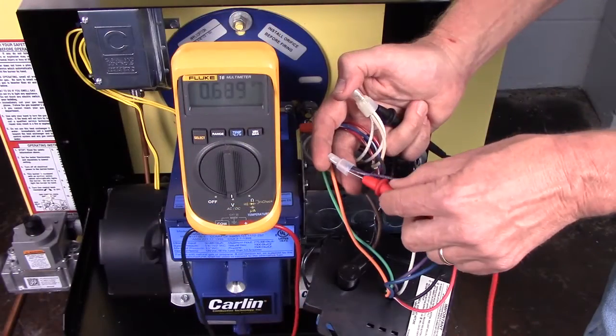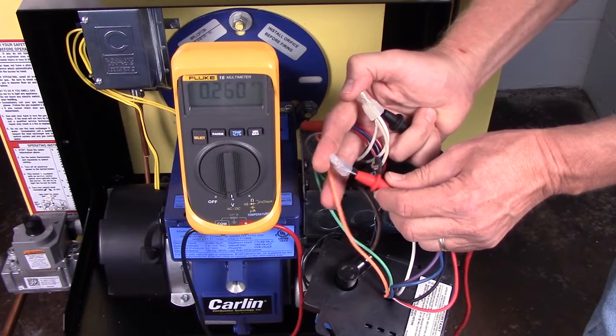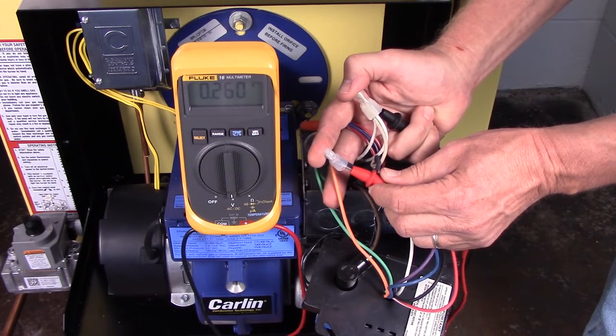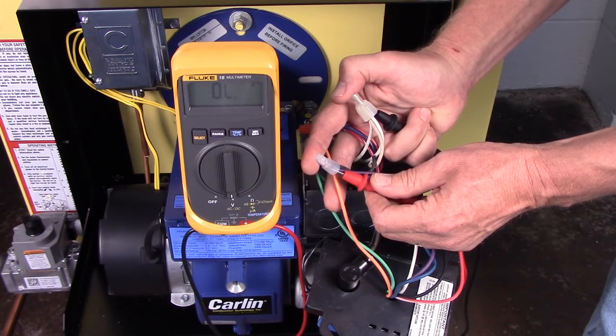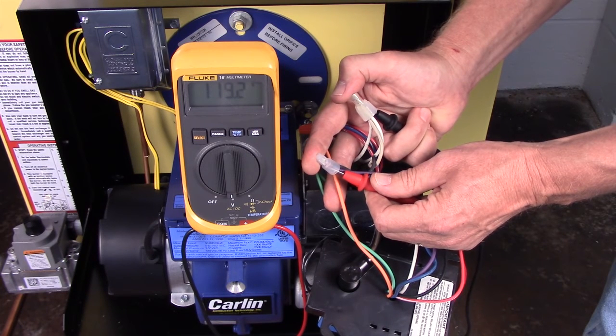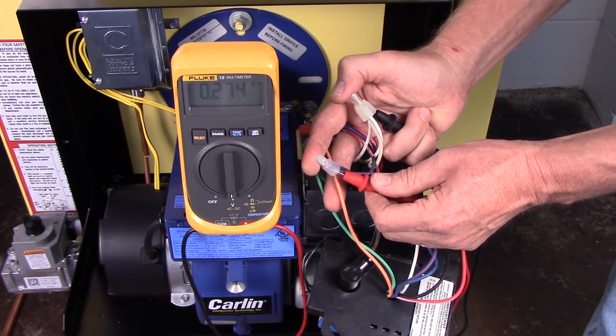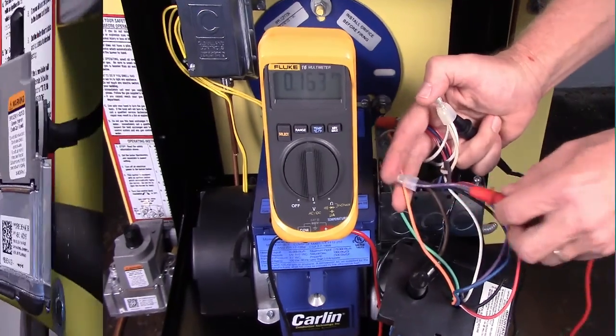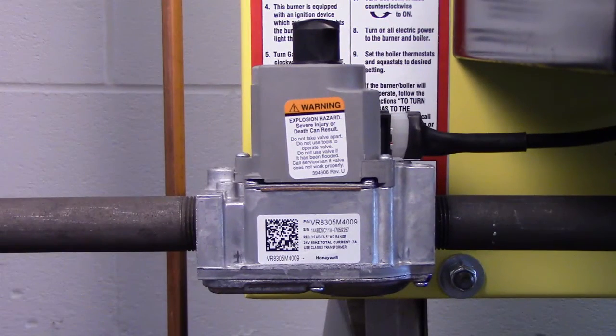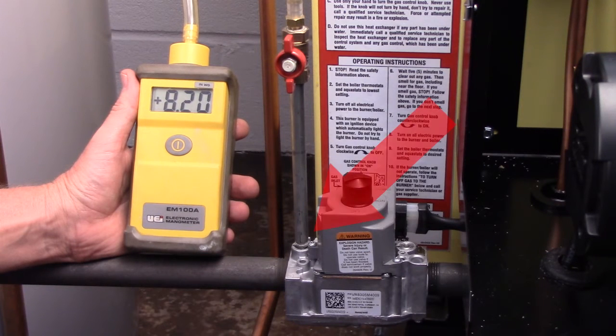Primary control operation should be checked by measuring voltage between the violet gas valve lead and neutral lead during the trial for ignition period. If 120 volts AC is not present during TFI, replace the control. Perhaps the issue involves the gas valve not opening. Check the gas supply pressure at the gas valve inlet.